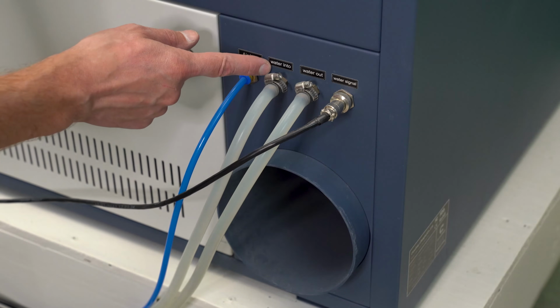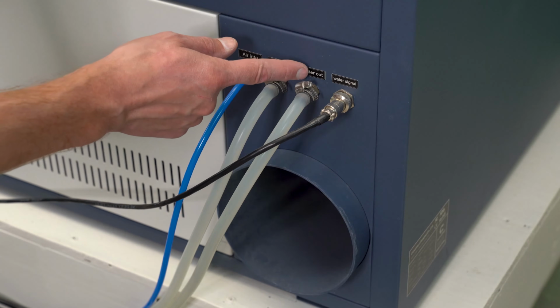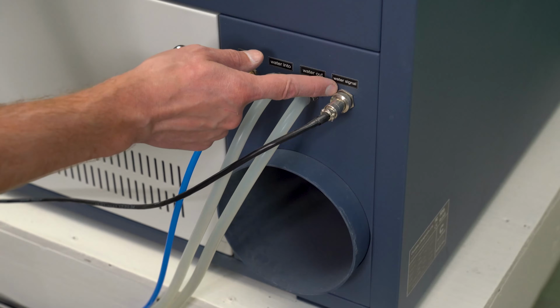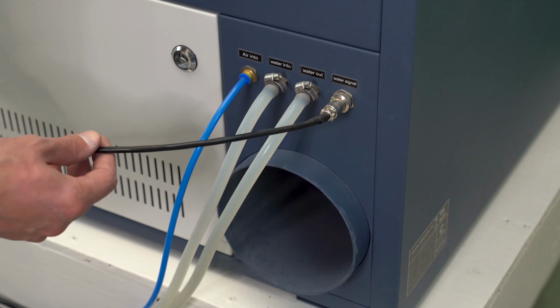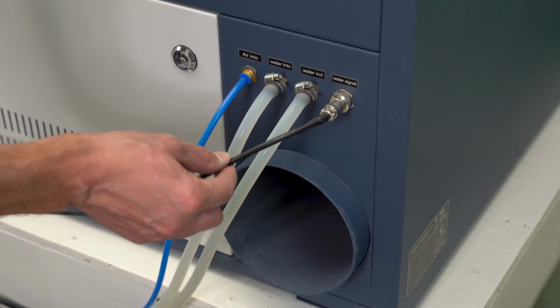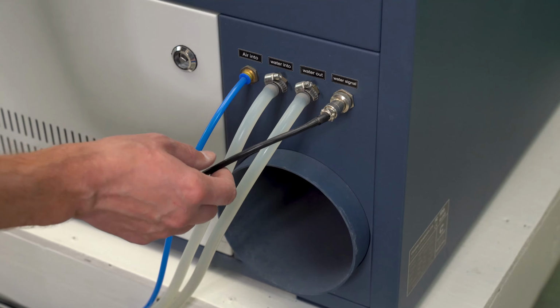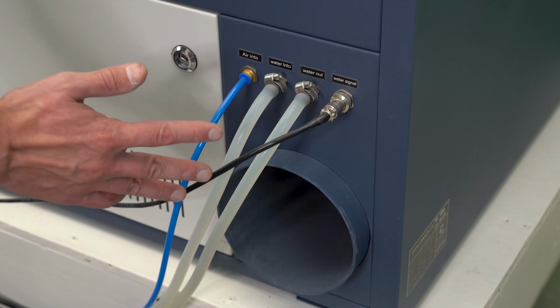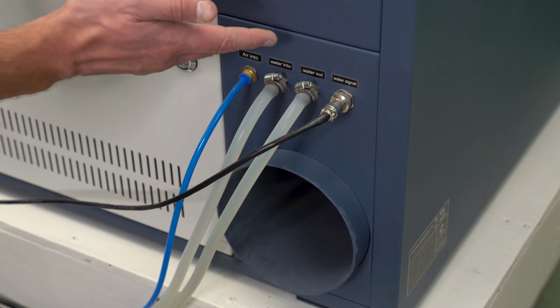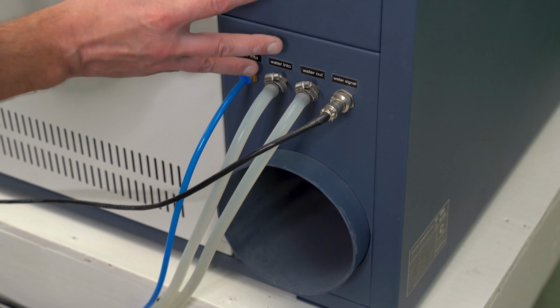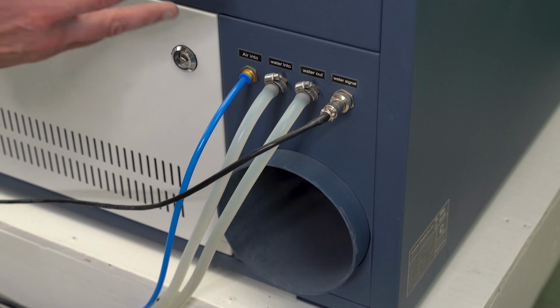They're clearly labeled as water in and water out, and here's the water signal. We're going to take a look at the water chiller, but this is the alarm cable from the water chiller. So if anything happens to the water chiller, it will alarm this machine and turn off the laser.